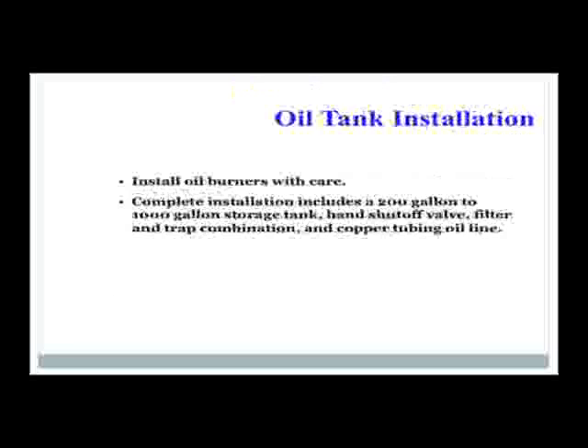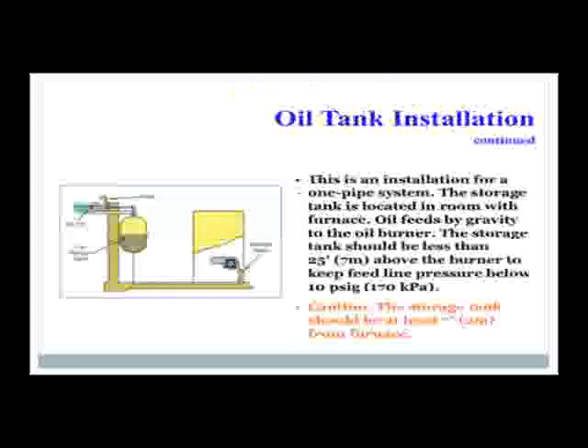Install oil burners with care. They need to be level and installed according to manufacturer's instructions. The complete installation includes a 200-gallon to 1,000-gallon oil tank, hand shutoff valve, filter and trap combination, and copper oil tubing. This installation pictured here is for a one-pipe system. The storage tank is located in the room with the furnace. Oil feeds by gravity to the oil burner. The storage tank should be less than 25 feet above the burner to keep the line pressure below 10 psi. The storage tank must be at least 7 foot from the furnace.